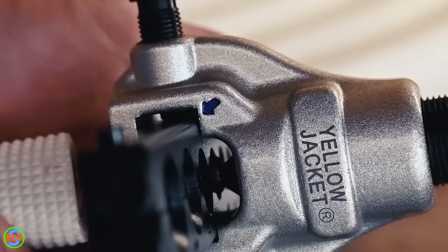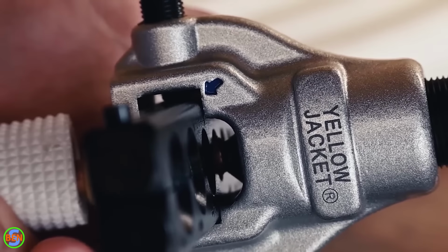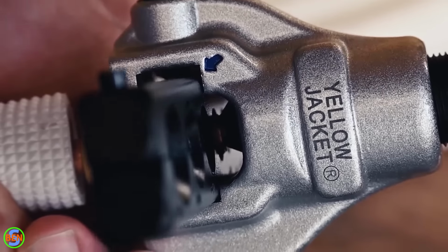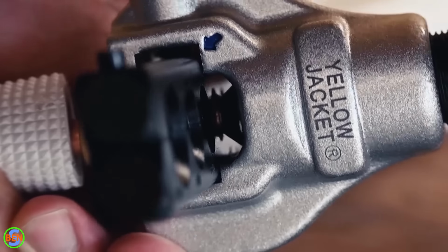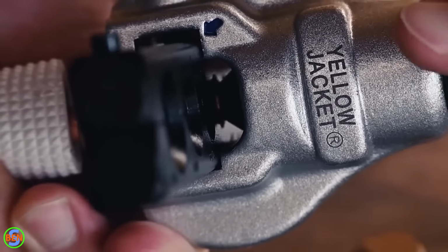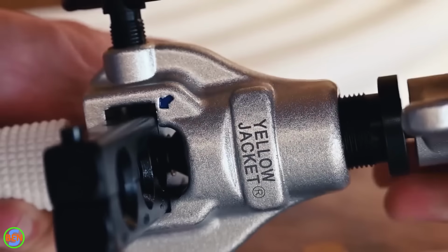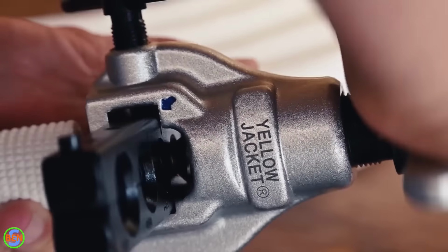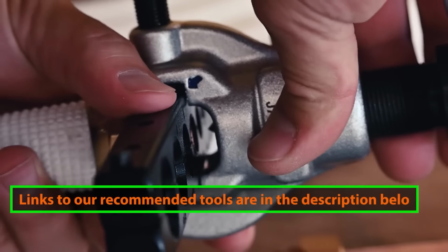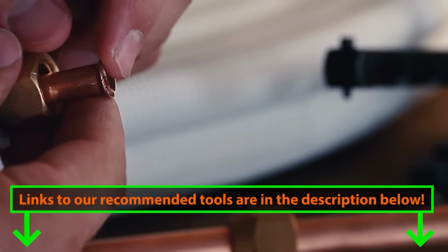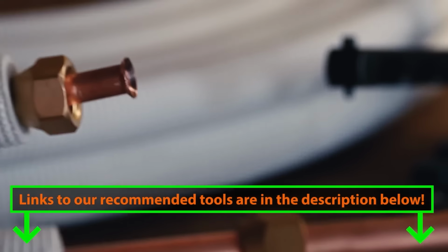See how it kind of rolls around in a circular motion? That is what allows this thing to make a higher quality flare than a standard flaring tool, which would normally just mash that cone right down into the end of the pipe. And that's it right there. We'll back it off, loosen the clamp, slide this back, open up the tool, and there we have our flare.